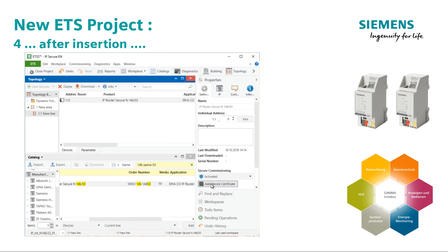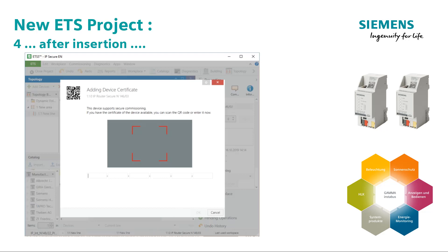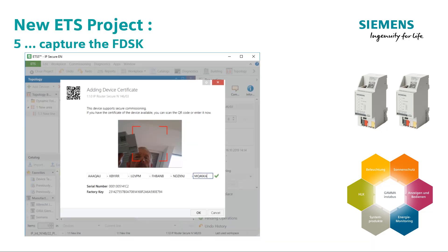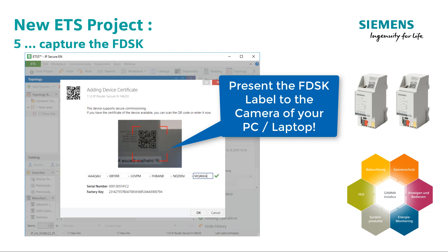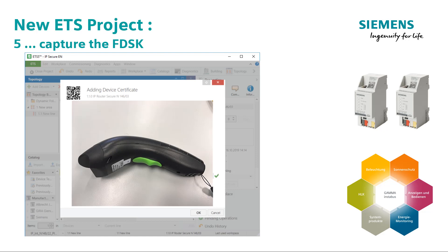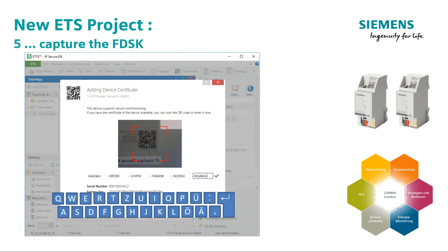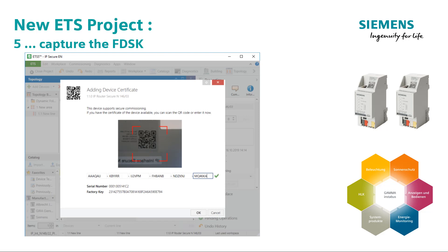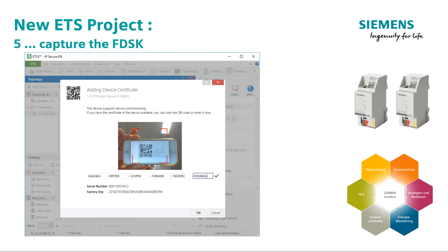As soon as you insert the router, you will be prompted to capture the FDSK. The easiest way to do this is to use the QR code scan method integrated in ETS via the camera integrated in every PC or laptop today. Alternatively, a QR code scanner or, as an emergency solution, the keyboard. With the 30-digit codes, however, this is very laborious if you don't only have to integrate one router.